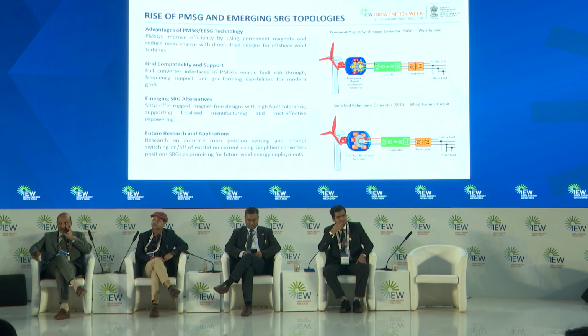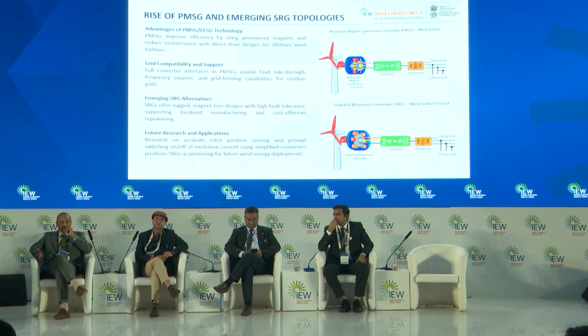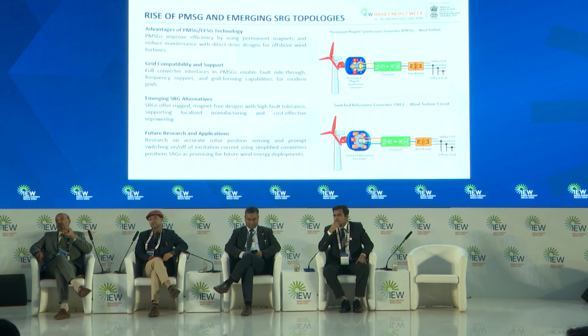Although it accounts for 30% of the current fleet in India, and although the full converter PMSG technologies are technically capable of grid forming, they are operated as grid following due to limitations like the energy buffer. As the grid is intermittent, to become a grid forming type, we should also have an energy buffer in case of any additional energy requirement. The system should be able to be supplied.